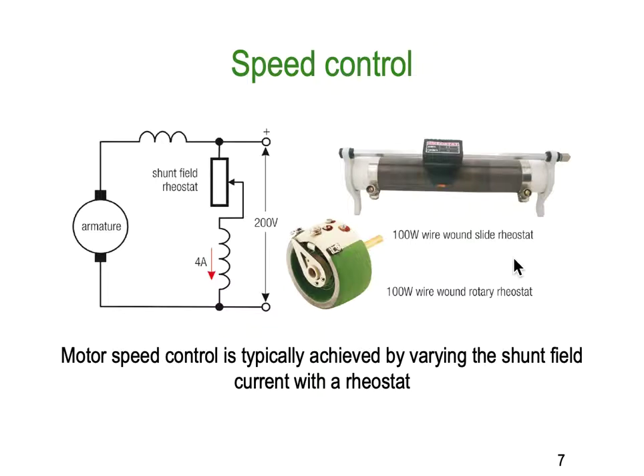Speed control. The best way to do speed control is by controlling the current through the field. We could control the current through the armature, but the current through the armature is normally very, very high — as you can see from our last example, it gets up in the order of 400 amps — where the field is only about 4 amps. So we tend to put the speed control in the field. You can see here a wound wire rheostat. We've got one end of the resistor here, the other here, and the common is up here. As we slide this backwards and forwards, we can vary the amount of windings in the resistor and therefore control the value of resistance. That's a 100-watt wire-wound slide rheostat.